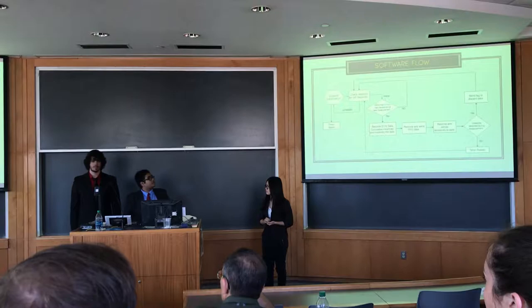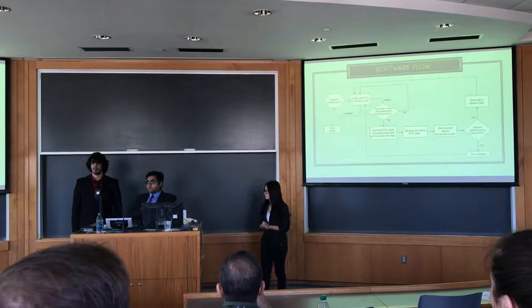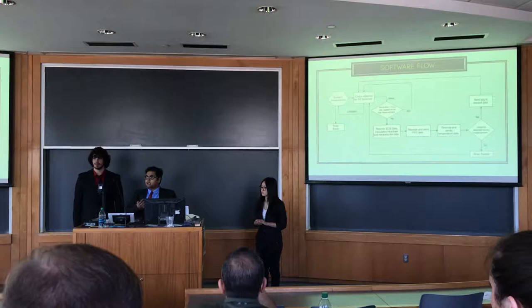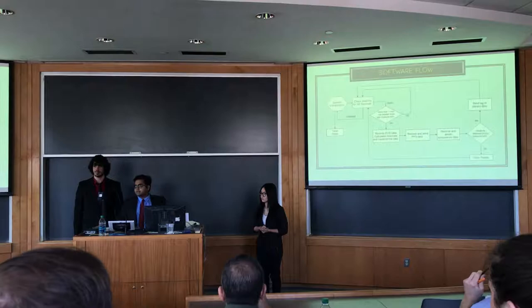So this one is actually for the wearable version, not for the portable version. For the portable version, you just click a button and it collects the data immediately. For the wearable version, because you are monitoring continuously, you don't need the patients to wait for this collection to start. If you are on the run and it detects that you are stable, it just goes to the collection. And to make sure that you are actually stable, it just waits for those 6 seconds.